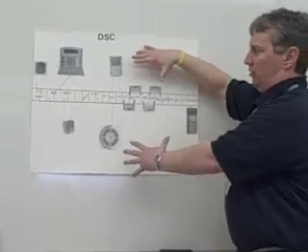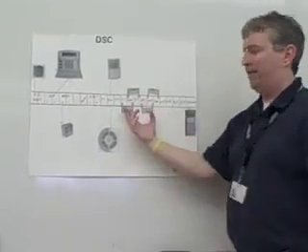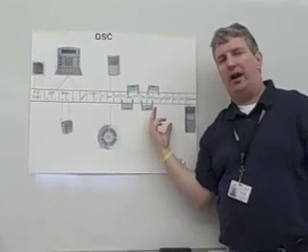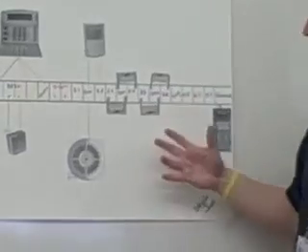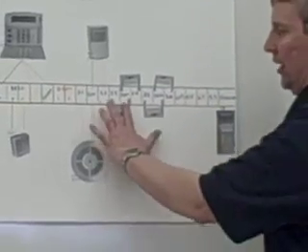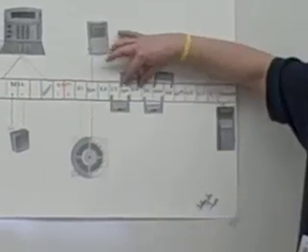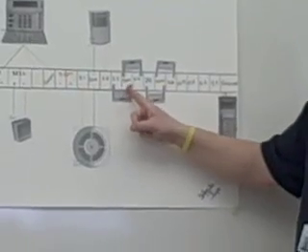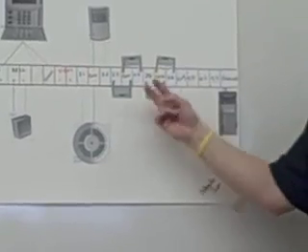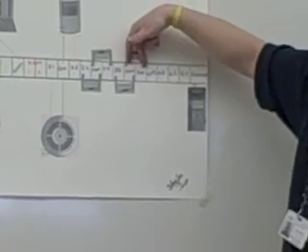Now, Chelsea's only hooked up two sensors. We left the rest of them open so that we can show you how these 2.2K resistors work. All a resistor is, is we're going to put the resistors in the zones that aren't being used. Z3 and COM, we put a resistor in. Z4 and COM, resistor. Z5 and COM, resistor. Z6 and COM, resistor.